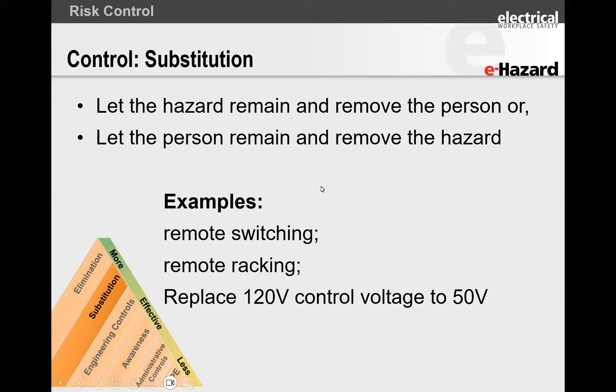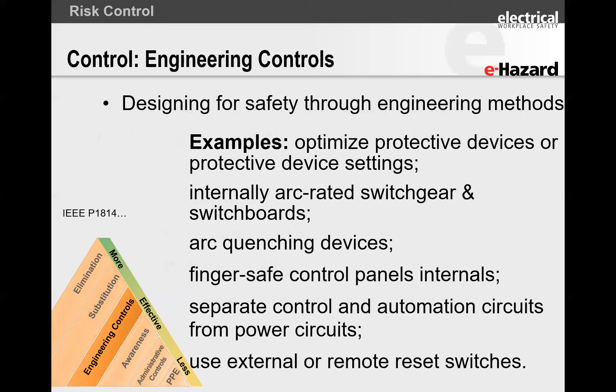The next one is substitution. Substitution means I'm going to substitute the person with something, or substitute the hazard with something. Instead of standing in front of equipment and pushing a start-stop button, depending on the arc flash energy, maybe I implement remote switching — a long lanyard that takes me away from the equipment. I could have remote racking, automated controls, or use a long lanyard. The best substitution: why are we still using 120-volt control systems? If you get your control voltage down to less than 50 volts, you win — because less than 50 volts means no shock hazard and no arc flash hazard.